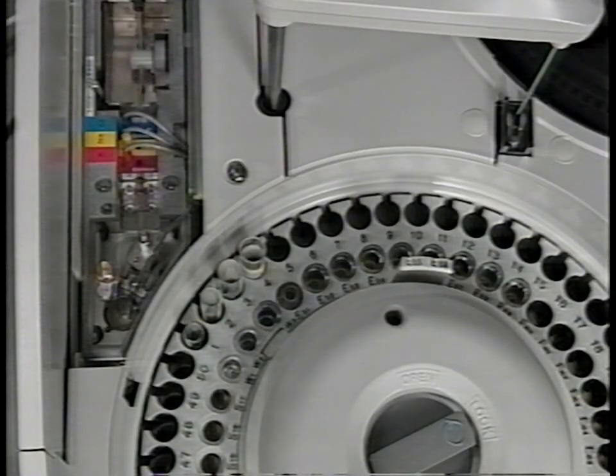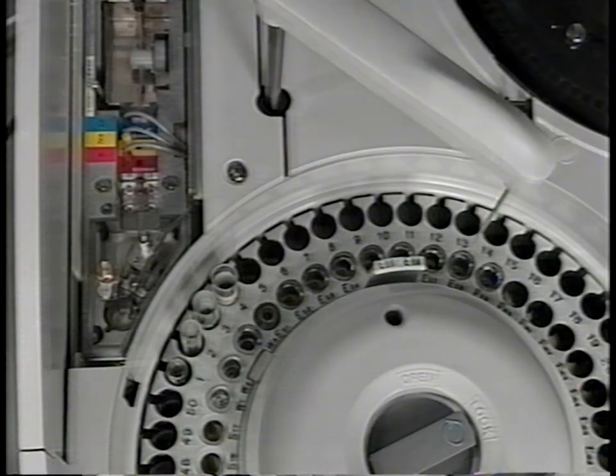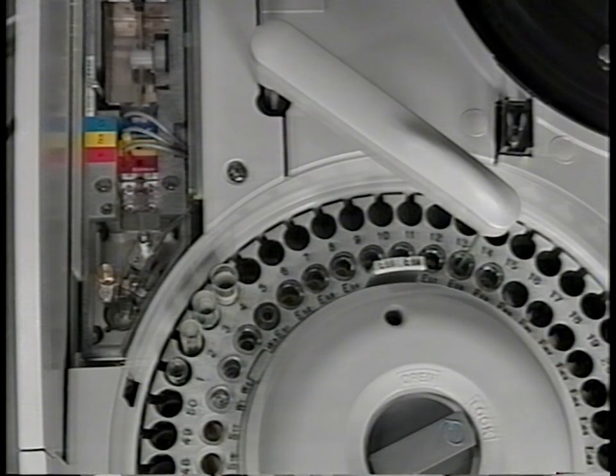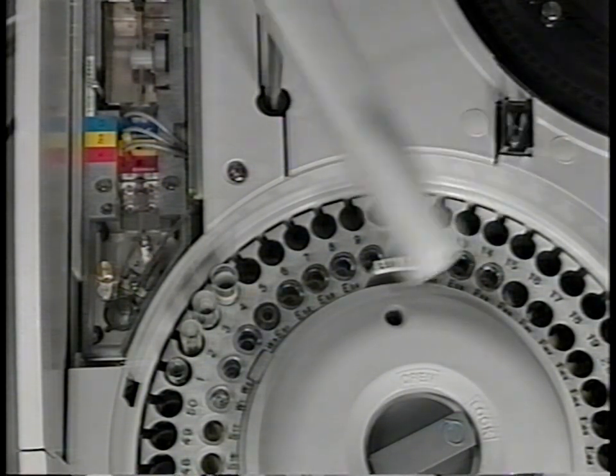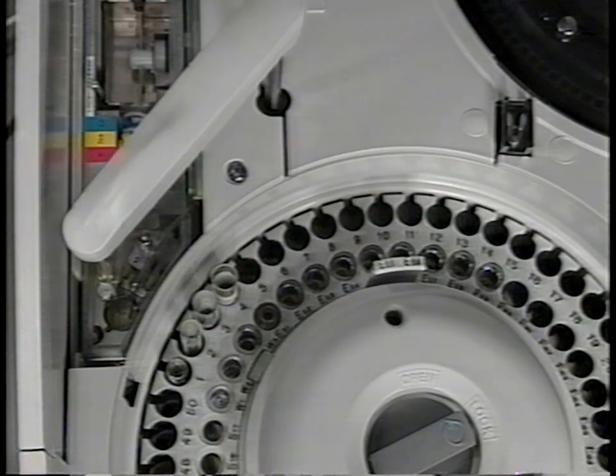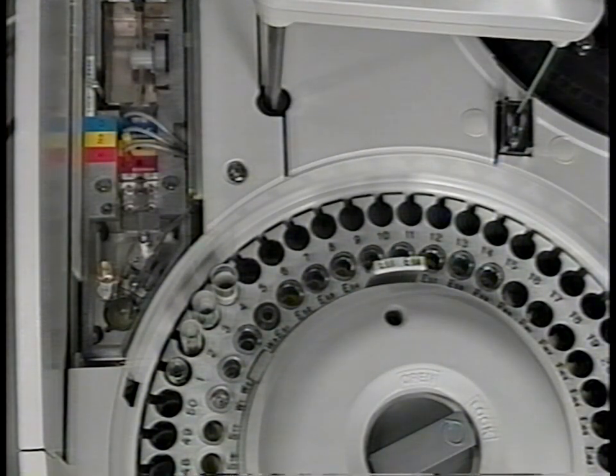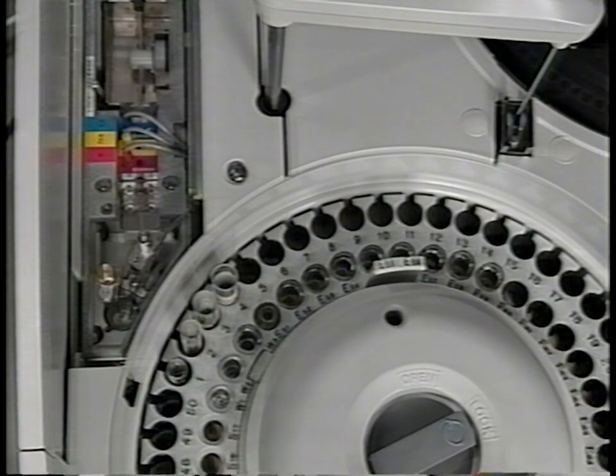Now that we've covered the location and general purposes of the basic ISE components, let's see how a sample is processed by the system. The sample probe aspirates sample. It then moves to the dilution vessel and dispenses 15 microliters of sample into it. Once the sample is in the dilution vessel, diluent is added to the vessel. Then the diluted sample is drawn into the flow-through ISE measuring cartridges by the action of a sipper syringe.